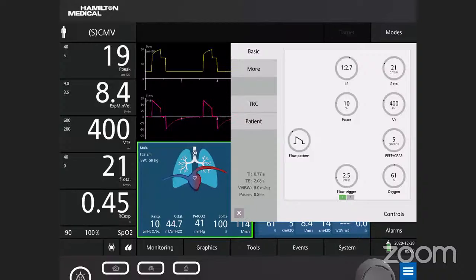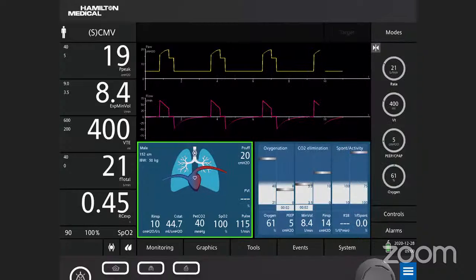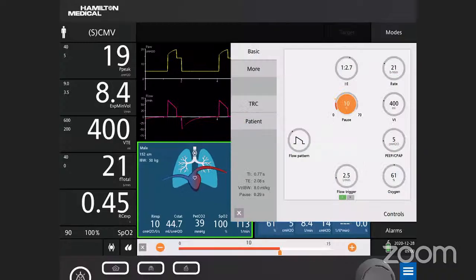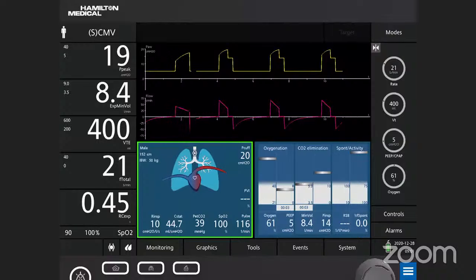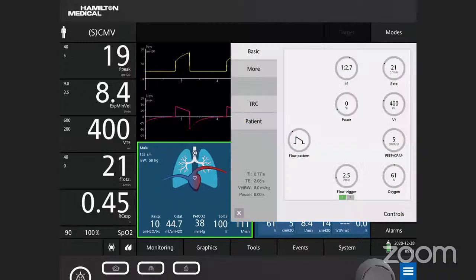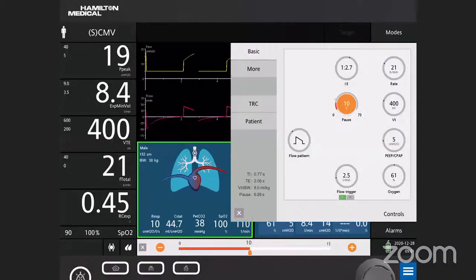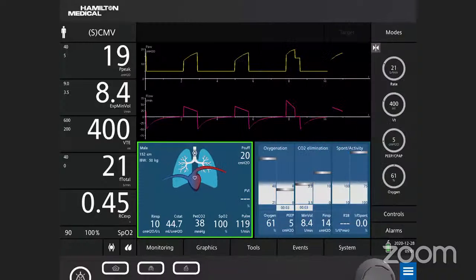Now the flow pattern, if you look here, you can see that it is a descending ramp pattern. But unfortunately, in this simulator you cannot change the flow pattern. If you change the flow pattern, it will switch off. So just look at the yellow tracing on the top. You can see a peak inspiratory pressure as well as the plateau pressure, correct? Now suppose I remove the pause time, make it 0, no pause. There is a change in the waveform. You can see there is only peak inspiratory pressure. So it is very important when you have volume control ventilation to give at least 10% inspiratory time hold. Then you will get both the peak inspiratory pressure as well as the plateau pressure, right?